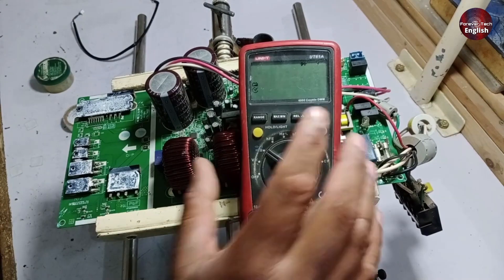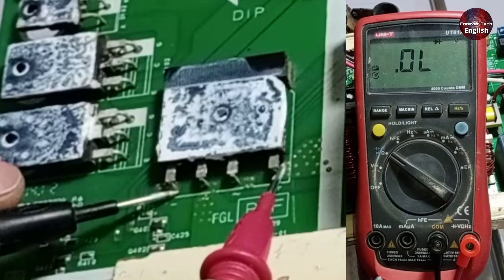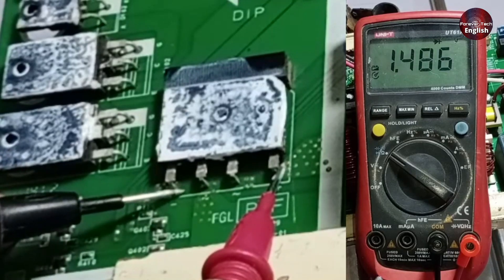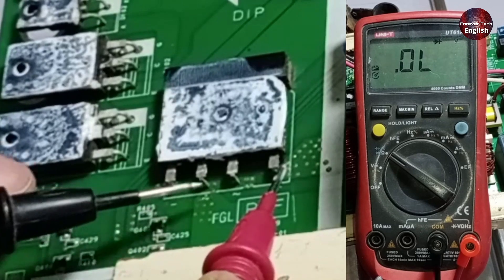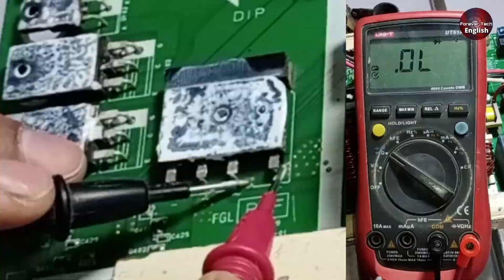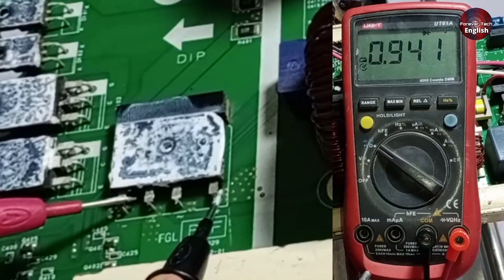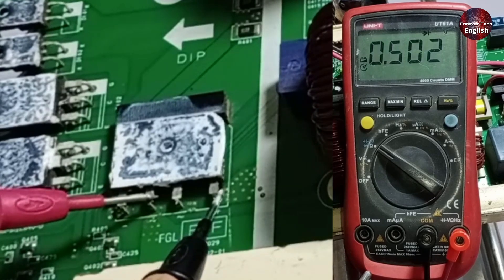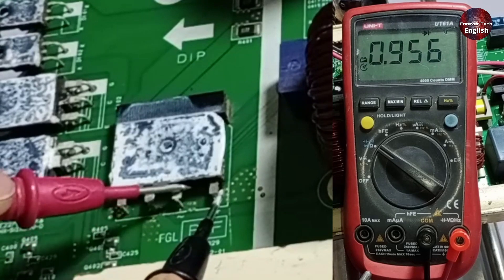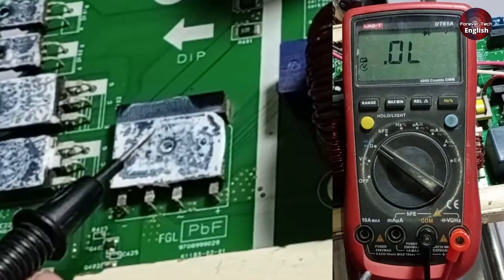To do this, set your multimeter to diode mode. First, place the positive lead on one side and the negative lead on the other. You should briefly see some voltage appear and then disappear. This means that this position is correct, and there should be no value showing at any other point. Then switch the probes and check again, and we are getting 0.940 voltage drop, which means this is working fine. At the next point, we get 0.502 volts and the same voltage at the next point. This means the rectifier is perfectly fine, and there is no issue.